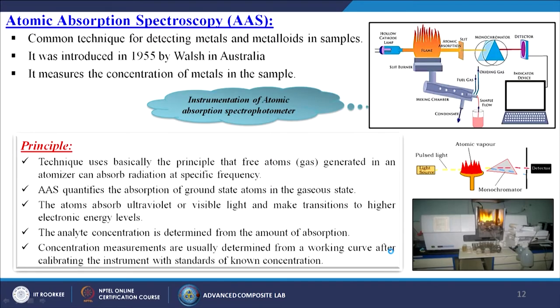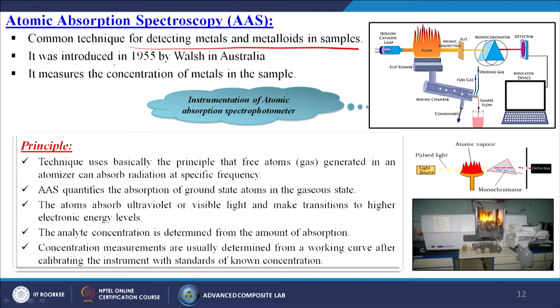The next technique is called atomic absorption spectroscopy, in short AAS. It is a common technique for detecting metals and metalloids in samples. It was introduced in 1955 by Walsh in Australia. It measures the concentration of metals in the sample. The instrumentation of the atomic absorption spectrophotometer consists of: a hollow cathode lamp, then a burner where the sample is burned, then atomic absorption takes place, then a slit, then a monochromator, then a detector. There is a mixing chamber and sample flow, and fuel gas and oxidizing gas are introduced. Data goes directly from the detector to the computer.